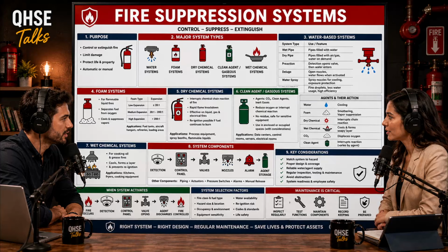Oh, I see. If you install a standard 135-degree sprinkler head directly above a blast furnace, the normal, everyday radiant heat is going to easily reach 140 or 150 degrees at the ceiling. So the standard sprinkler would activate constantly just from the normal manufacturing process. Precisely. You'd have catastrophic accidental discharges of water into a blast furnace, which would cause a massive steam explosion. That makes perfect sense. You match the sensor to the baseline environment.